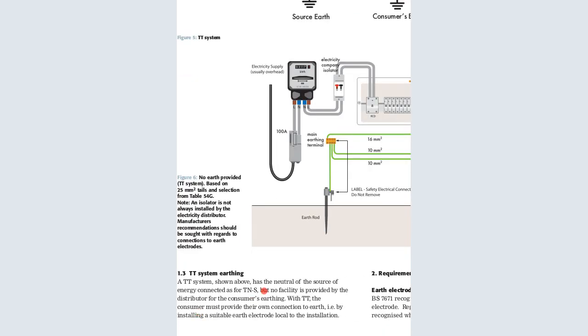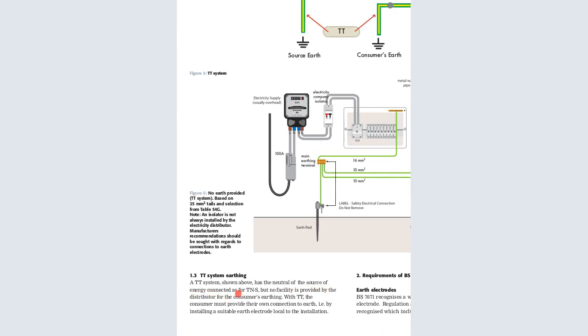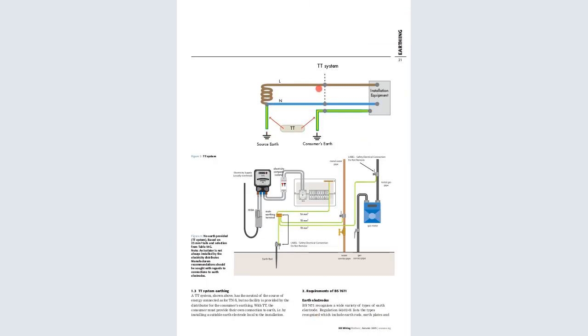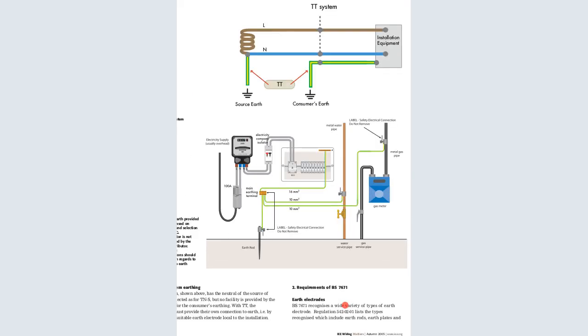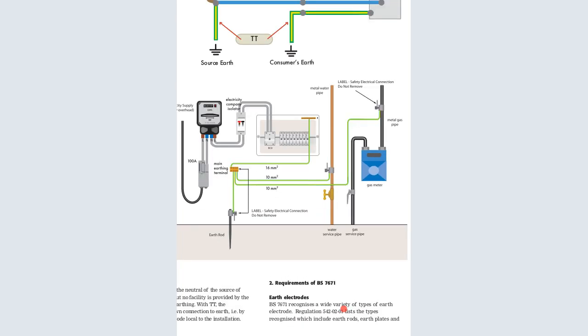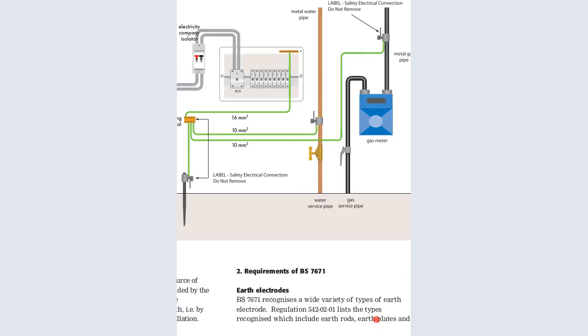So a TT system shown above has the neutral of the source energy connected as in the TN-S, but no facility is provided by the distributor for the consumer's earthing. So then with the TT, the consumer must provide their own connection to the earth, i.e. by installing a suitable earthing electrode, the local installation. So because they have not been provided, the earthing source by this supplier, like for example, Kenya Power, which distributes the power, at the point of offering the service cable, they don't provide the provision for the earth. So what happens? The consumer now has to provide and generate his own earthing, and that is what is seen here. So that is called the TT system. So the requirements of the BS standard, these are the standard code or the IEE regulation standards, are needed for earthing.